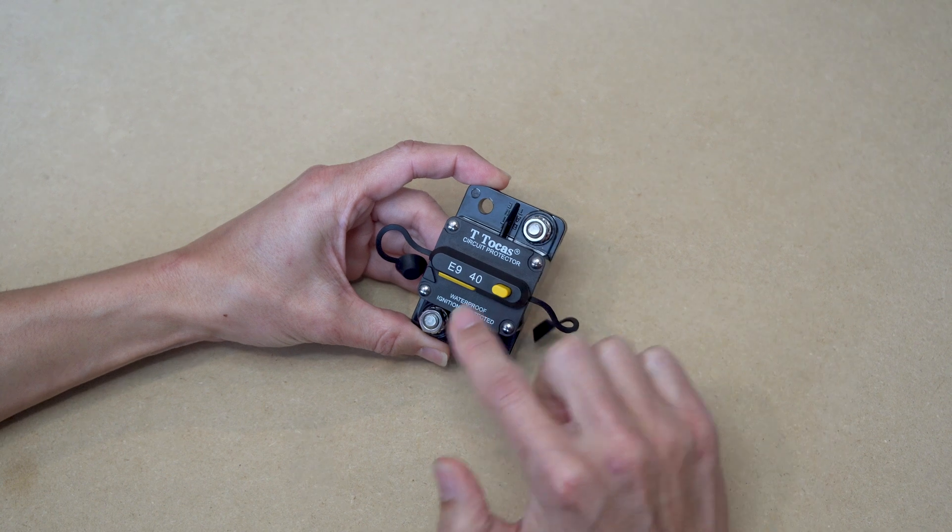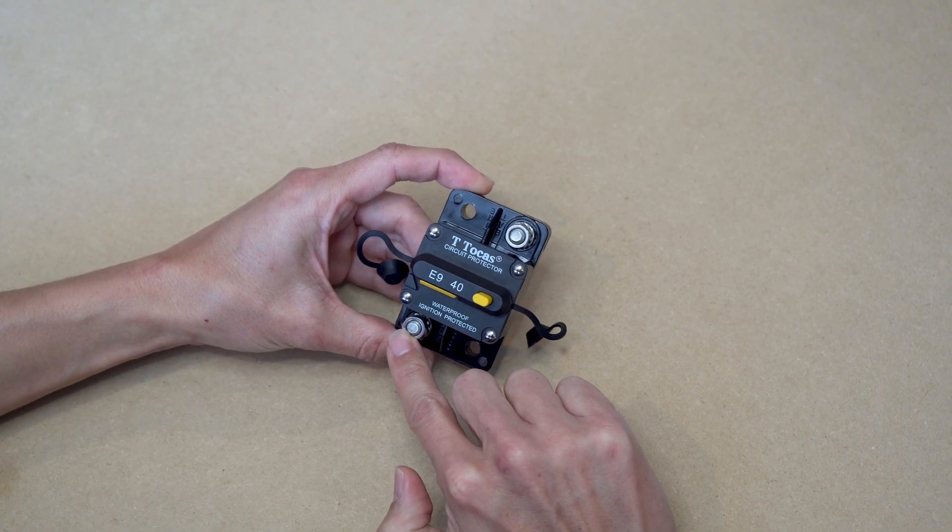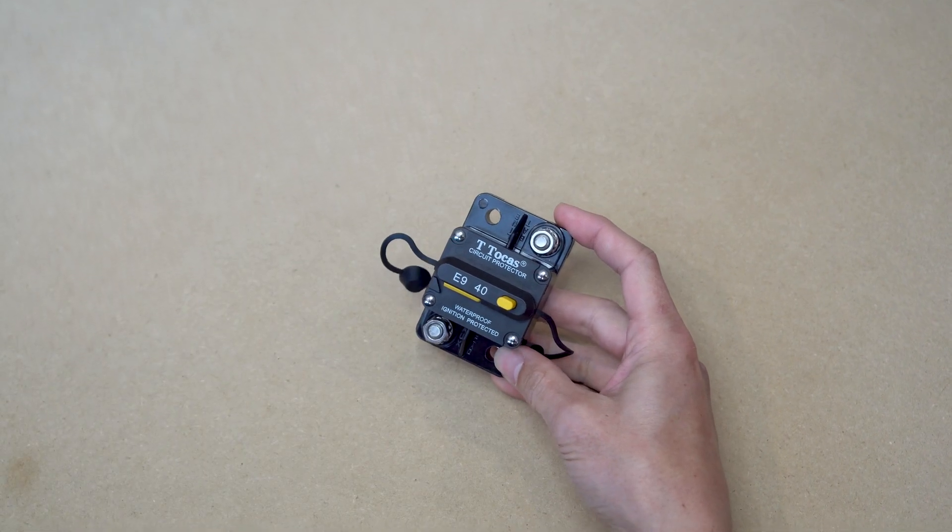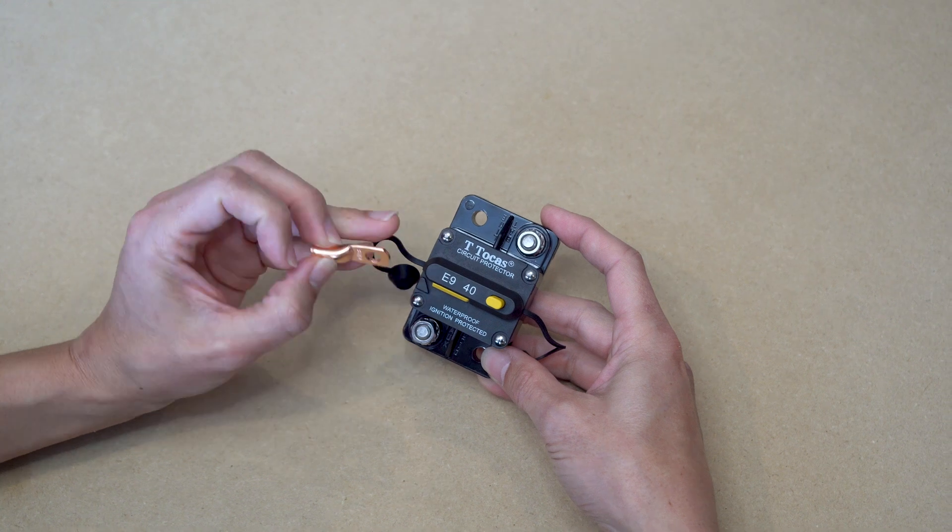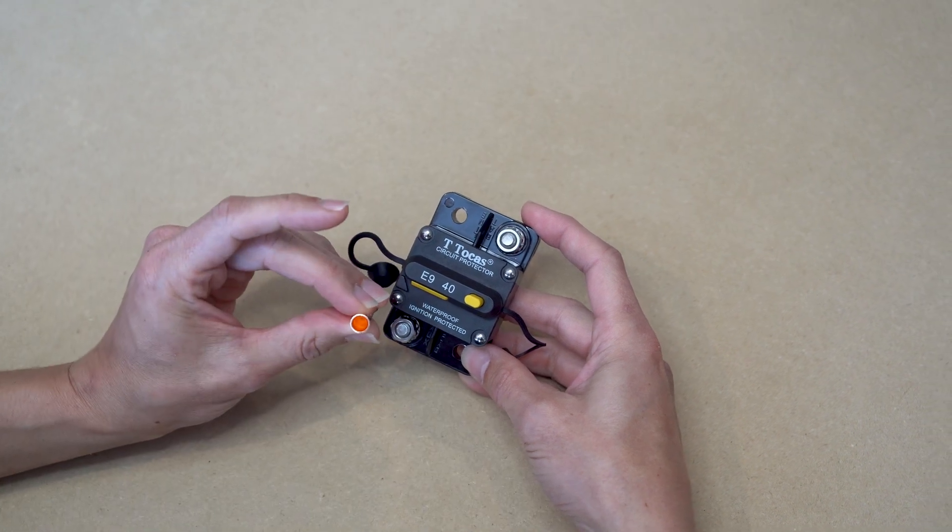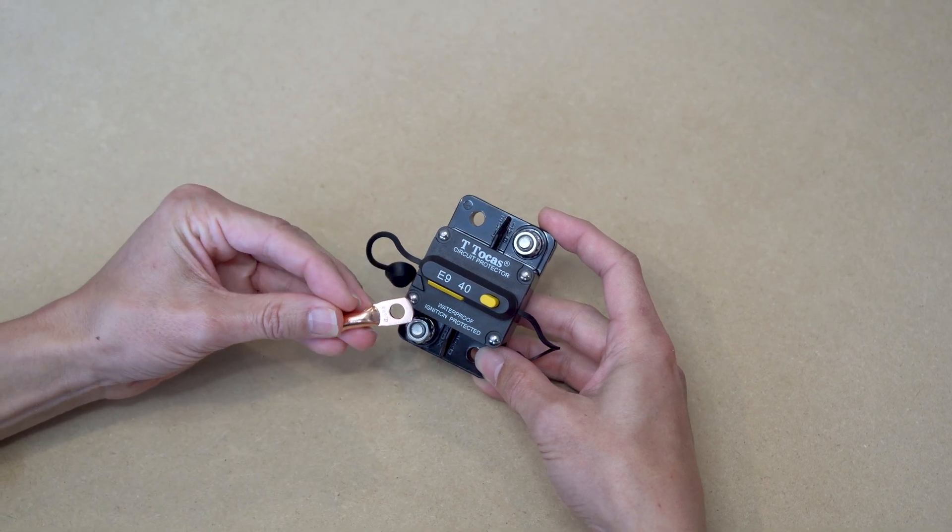These are quarter of an inch terminal posts. So to connect these posts to your wires, you'll need quarter of an inch terminal lugs. In this example, I'm going to use these quarter of an inch lugs, which accommodate 8 gauge wire. To make the connection, you'll first want to crimp this lug onto your wire.